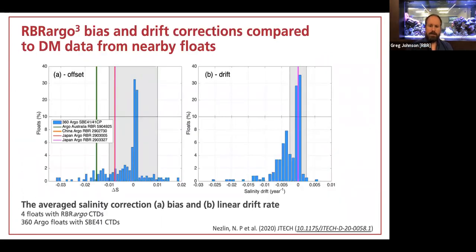The drift behavior of an inductive cell is quite interesting. The mechanism is not fully understood, but it seems to be constrained, and there is perhaps an initial aging period, and then the drift stops.